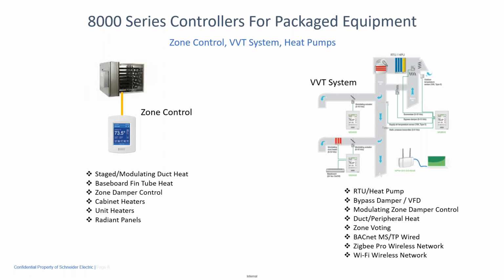Hey, the damper opens to allow hot or cold air depending upon what's coming down the duct. You can put in a supply air temperature sensor and use it that way. Typically utilized for, again, things like zone damper control, cabinet unit heaters, radiant panels.